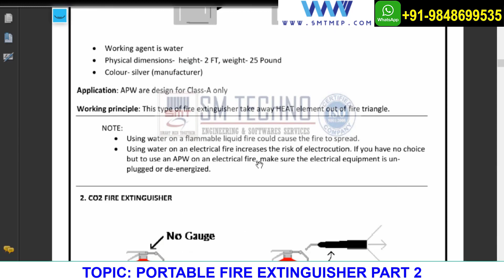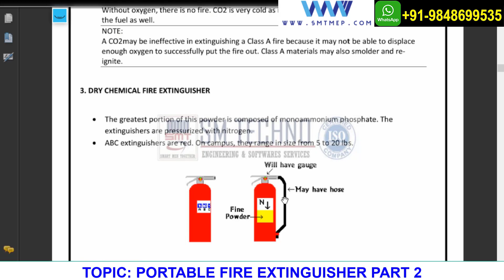But remember, I don't have much experience about the water type, but this CO2 we can use multiple times. Suppose I use it one time and within one spray the fire is controlled, we can use it another time. Anyhow, maintenance people must check that. But in case of this powder type, it's for one-time use. Once you use this, the pressure will drop, even though some powder is still available inside. So once we use it, charging is required again, so we cannot use it multiple times.